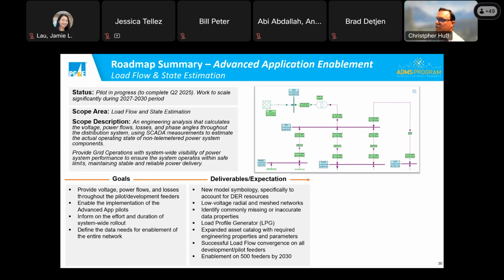Load flow state estimation utilizes various physics and electrical calculations to calculate throughout our system voltage, power flows, losses, phase angles, and VAR flow. This allows us to have visibility in areas where we don't currently have telemetry, and it utilizes our telemetry and matches that load flow to derive and get our real-time telemetry to match the core fundamentals of the physics properties of the system.